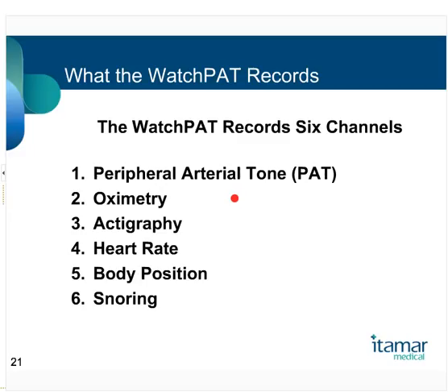The WatchPAT has the ability to record 6 channels. It records peripheral arterial tone, which we'll talk more about, oximetry, which is familiar to you, actigraphy, which is familiar to you. That is motion of the wrist or hand that the device is attached to as a measure of wakefulness versus sleep, heart rate, body position, and snoring. And it takes all of this information into its proprietary algorithm and comes up with a measurement of a variety of key signals that are a part of diagnosing sleep apnea.